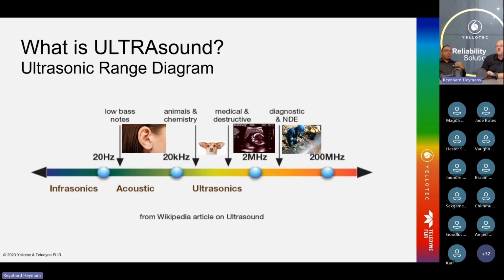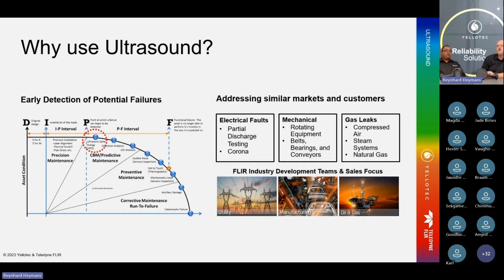It actually makes it a really good diagnostic tool. Some people are familiar with it in the medical space, but it's also good in the mechanical and electrical space. If we look at this predictive maintenance curve, you will see that the ultrasonic spike is one of the first things that can be detected. Because of this, you're able to look at electrical faults, mechanical faults, and gas or compressed air leak faults much earlier in the predictive maintenance scale.